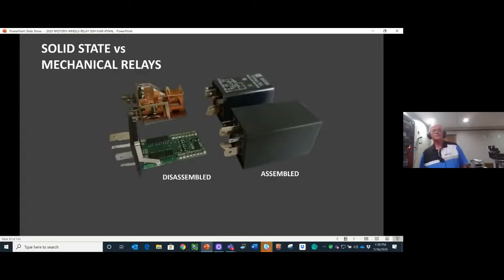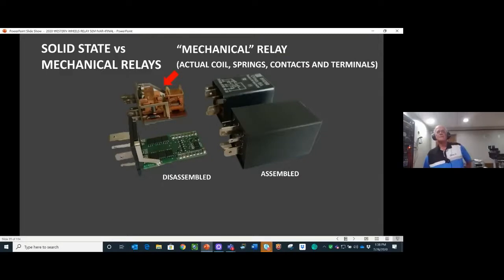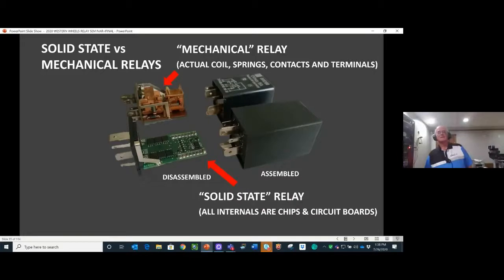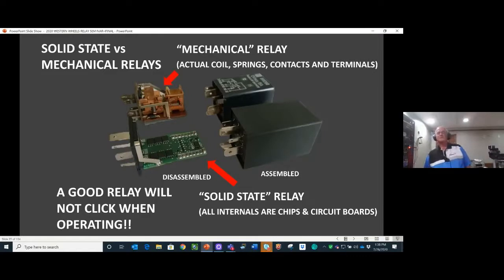If you took the covers off of a solid state and a mechanical relay, you would see the coil, you would see springs, you would see the armature, the contacts, and the terminal. If you took the cover off of an electronic solid state relay, all you see is the circuit board. No click.